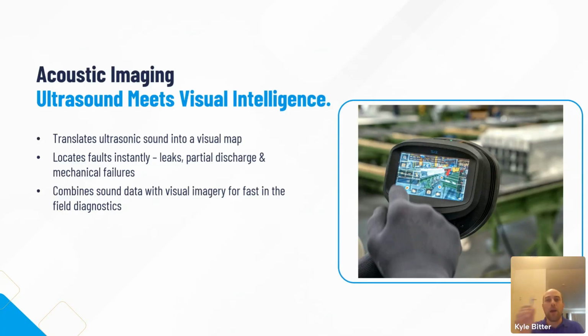You're now identifying, as you can see on the screen, where those leaks are coming from. You can quickly and precisely pinpoint the source, but it also helps eliminate false positives. If I'm scanning an area and see something reflecting off a solid surface like a wall or a hard cabinet, I know the wall isn't leaking, but there is definitely a leak in that area. It's up to us as inspectors to properly pinpoint where those leaks are coming from.